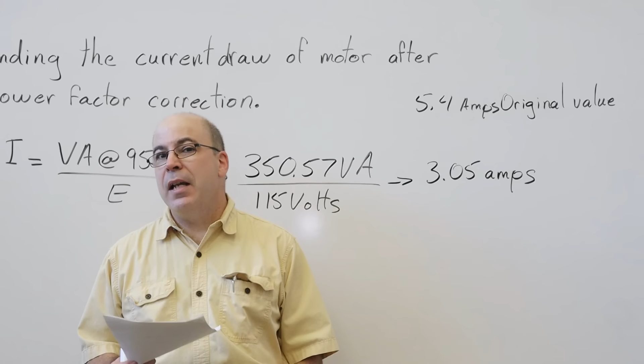Now, in order to facilitate things, I'm going to employ this line splitter. This device is going to allow me to plug it into our power supply, but it's going to allow me to use my clamp-on ammeter to get a current reading. I want to get current readings prior to doing any kind of power factor correction so we can get a baseline reading, and then after we've done our power factor correction, we're going to check the current again and see how much current we were able to eliminate coming from my power supply.